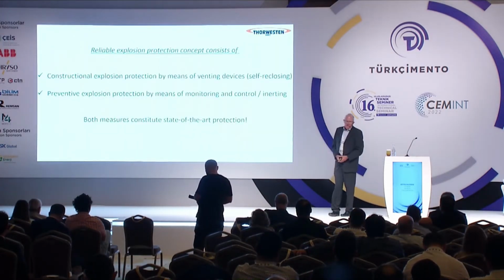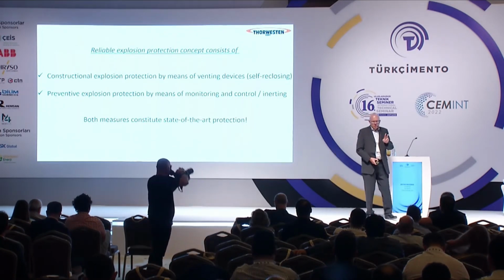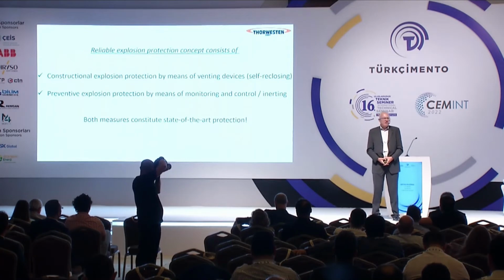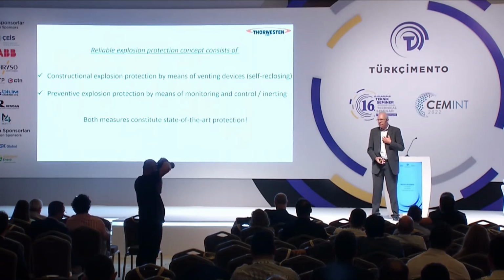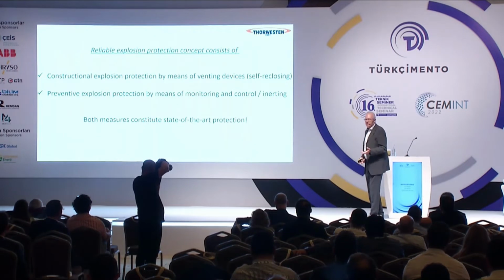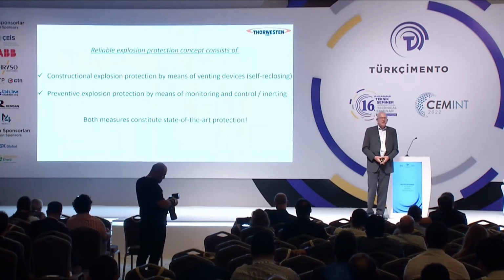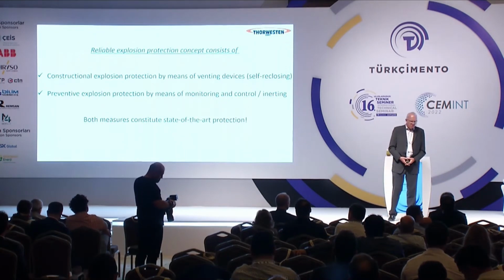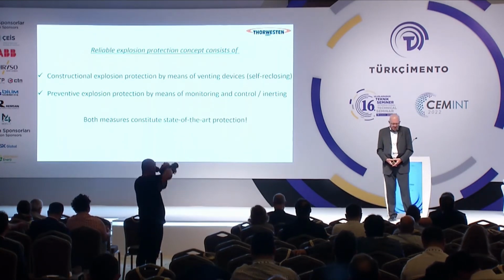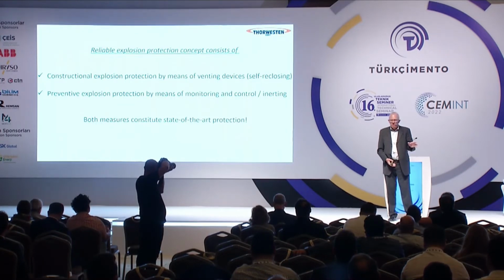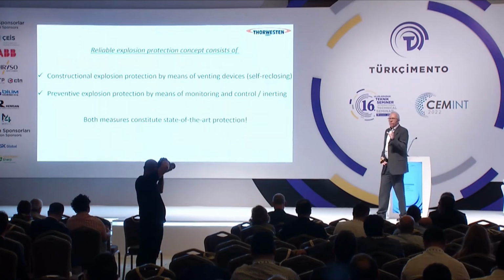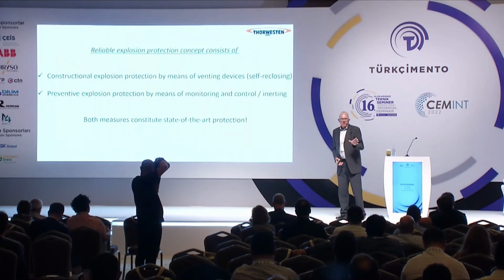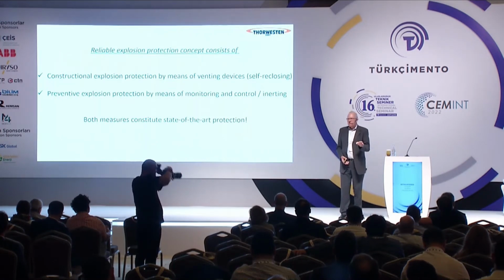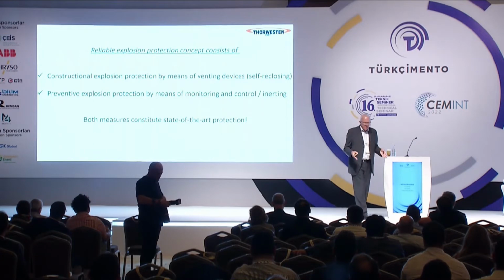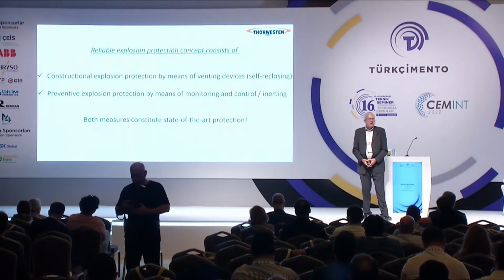A reliable explosion protection concept consists of two individual working systems. First of all, and this is my part from Thorwesten, the constructive explosion protection by means of venting, self-reclosing, reusable devices. The other part, covered by our partner company REMBE, is the preventive explosion protection in terms of monitoring, control, and inerting systems. Both systems represent state-of-the-art explosion protection. Don't get me wrong, it's not a question of either or.